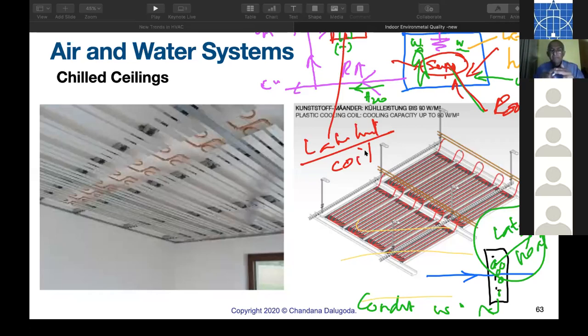The systems that don't have a return air duct, if it is an AHU directly coupled to return, RH cannot be brought down. So if you have not done this before, please do that and phone me, tell me what you have achieved. You have achieved wonderful comfort conditions. So we'll have to bring all the water vapor back to the cooling coil.